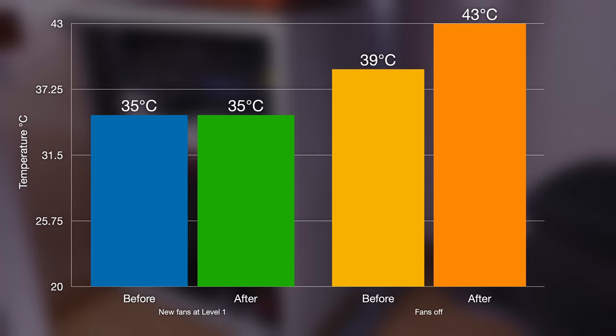Then if we look at both racks with the fans off, you can see quite a difference. Before, with the fans off, the rack reached around about 39 degrees. However, now with the fans off, the rack reaches 43 degrees. And that was only over maybe an hour or so. It might have gone up even more if I left it longer. And that really shows how the sound insulation is also thermally insulating the rack.